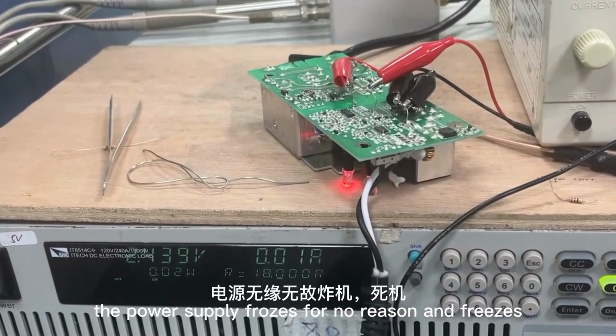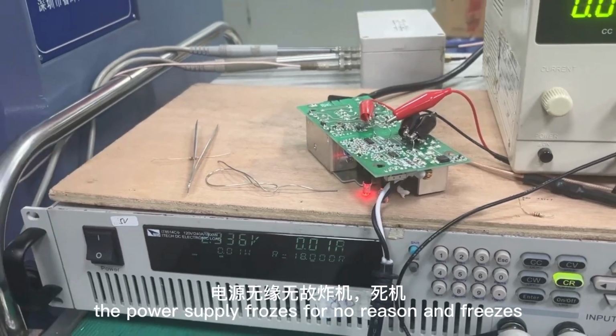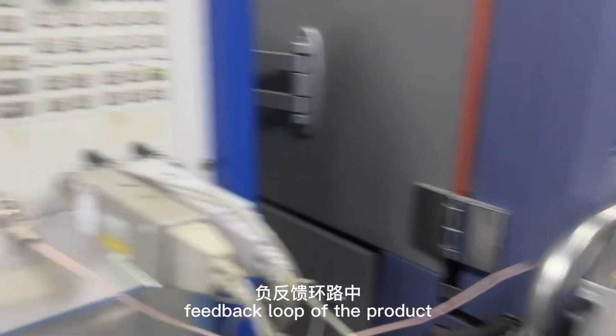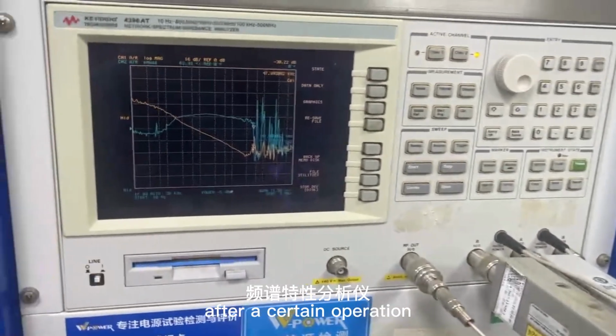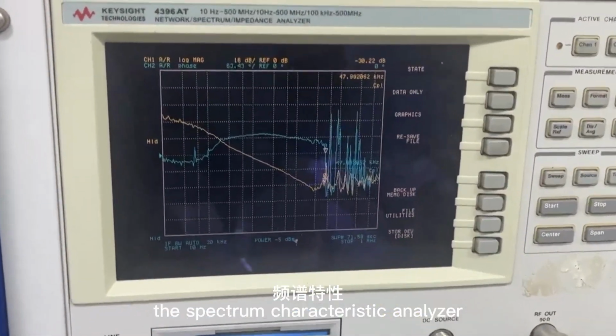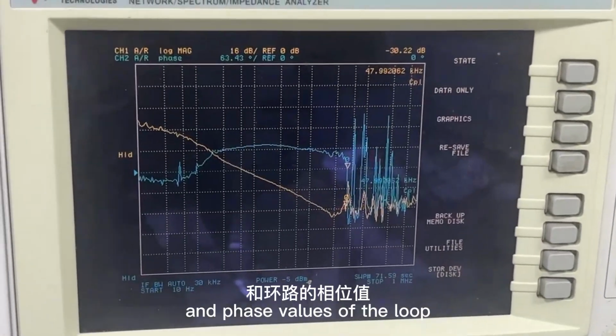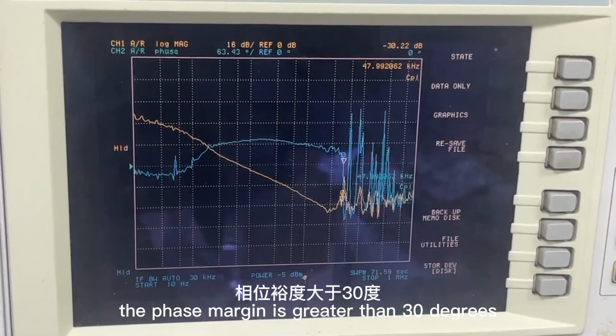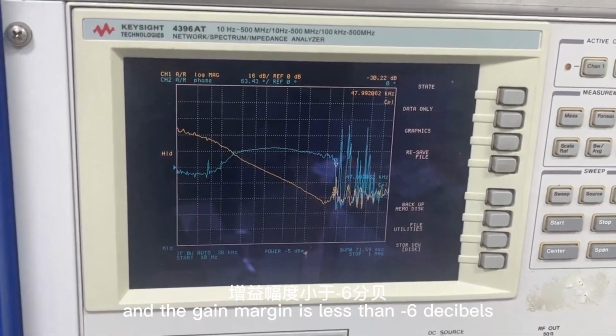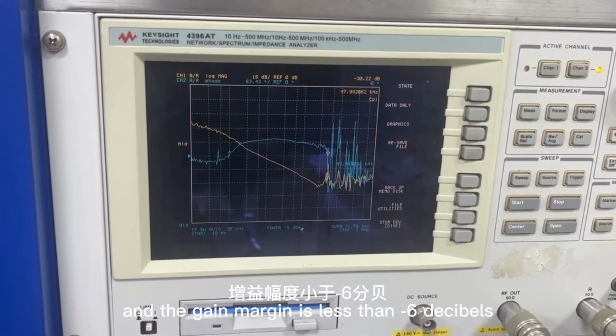Significance of loop stability test. The power supply freezes for no reason. The signal is injected into the negative feedback loop of the product. After a certain operation, the spectrum characteristic analyzer calculates the gain and phase values of the loop. The phase margin should be greater than 30 degrees, and the gain margin should be less than -6 decibels.